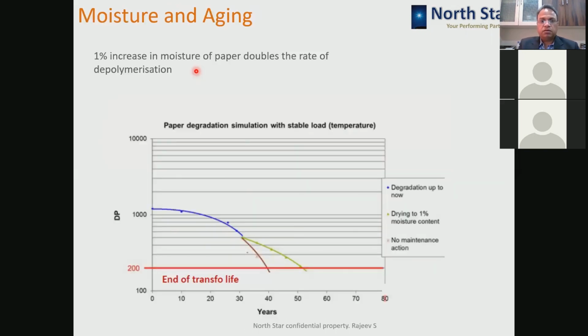Okay, now moisture and aging. There is one thumb rule that if you increase the moisture inside the transformer, then every 1% increase in the moisture of the paper doubles the aging of the transformer. So paper starts decomposing 2 times faster. So if you control the moisture inside the transformer, then the transformer life will be more.